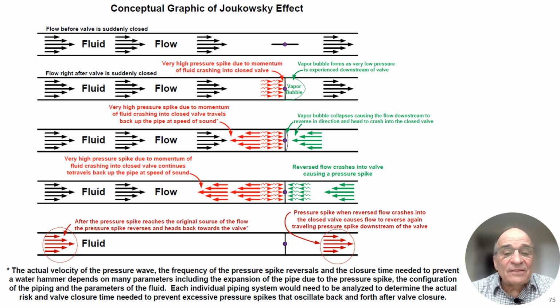Now, that is if the pipe is totally rigid. If the pipe is not totally rigid, that pressure spike dissipates as it goes back. But depending upon how rigid that pipe is, there certainly will be a spike of pressure that goes back to the source of the LNG. So now you have this pressure spike, which I'm showing here as a double set of lines continuing back. Now that gets to the other end of the pipe and it goes back again.